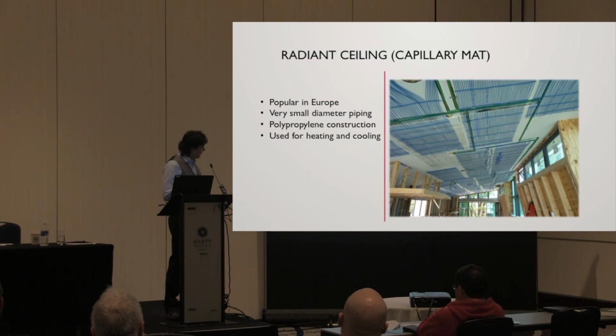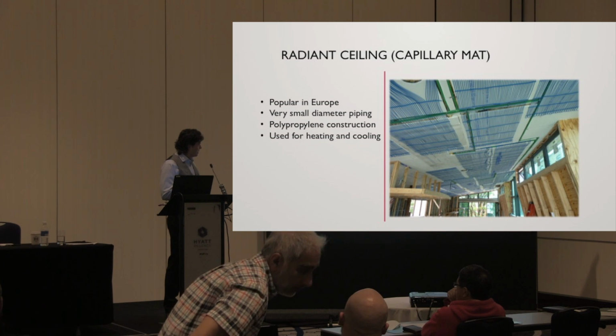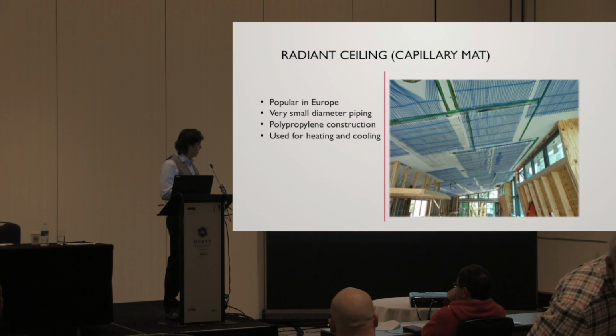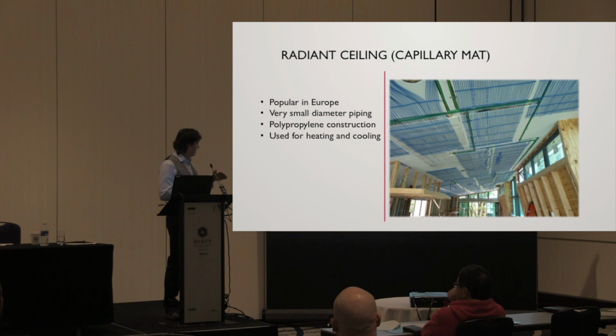So you get the heating and the cooling. Well, it's not the worst case scenario for cooling when you think about it. I've actually put some of these in a commercial application before. They're polypropylene. They don't have an air barrier, so they do tend to entrain oxygen into them. So you have to have air removal systems, like any other radiant system, but they're a little more prone to it. And of course, pumping requirements, because the tubing is such a small diameter, it's quite a bit to pump through there. The Europeans love them.